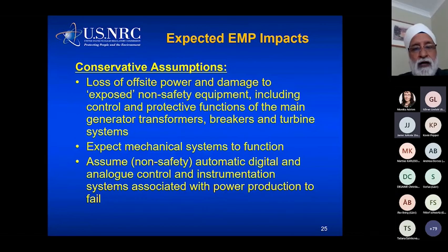So we assume the loss of offsite power and we damage all non-safety equipment. In other words, all our relays are gone, all our protective functions are gone, breakers don't function. Maybe we damage the main generators, and breakers and turbine systems, electric systems do not function. However, we do expect mechanical systems to function. We do not rely on automatic digital and analog control and instrumentation systems because they're mostly associated with power production. We are interested in safely shutting the plant down.